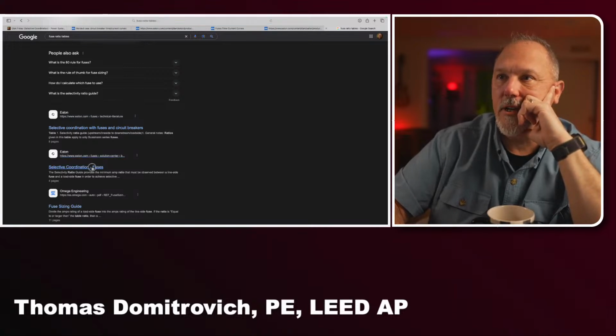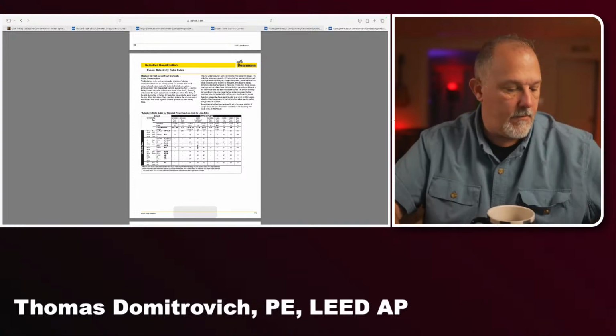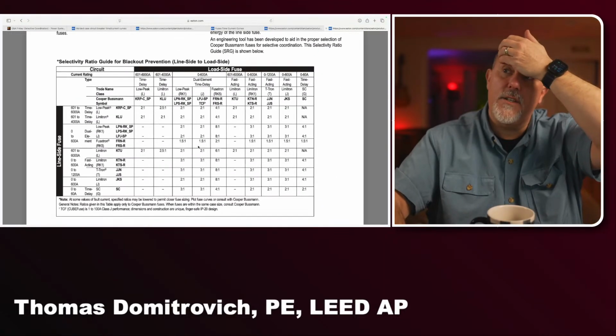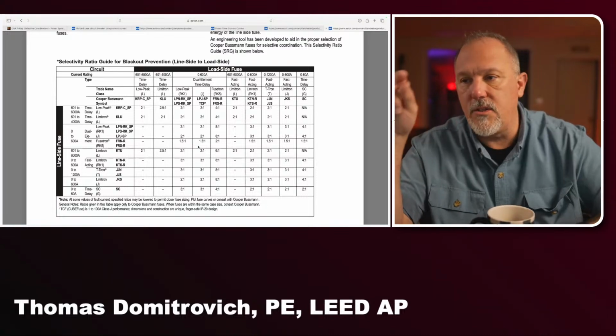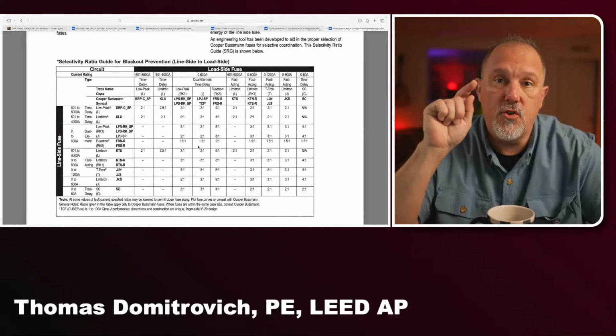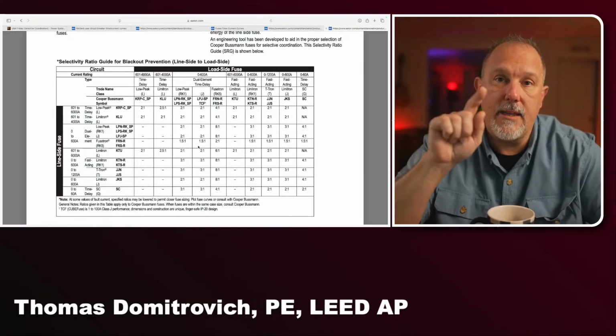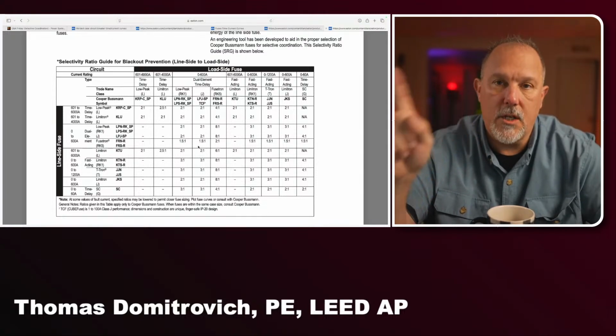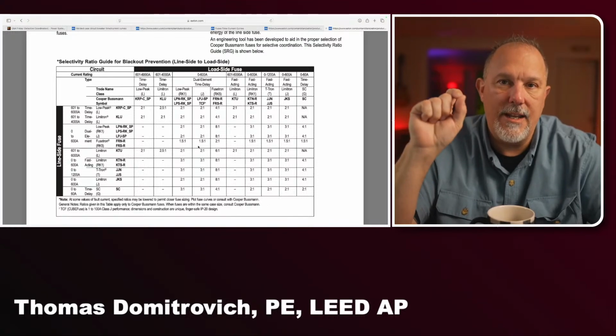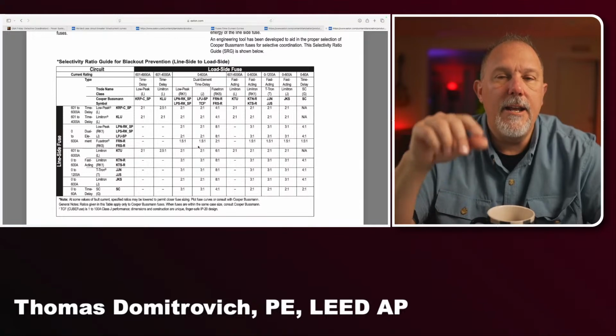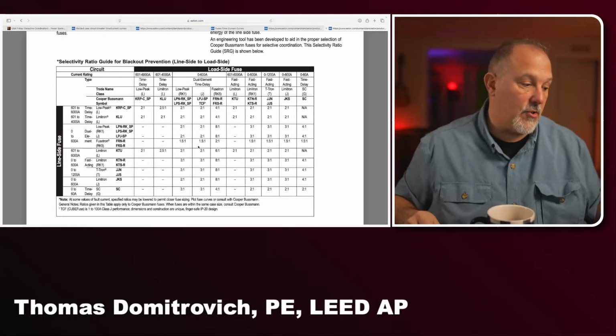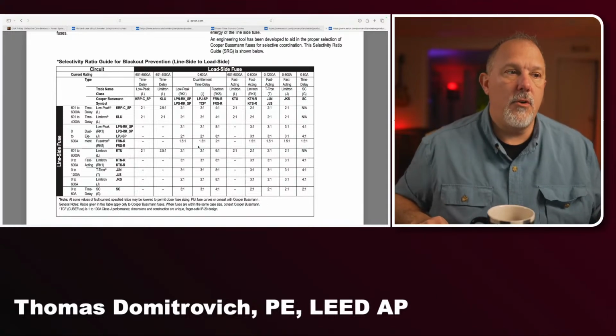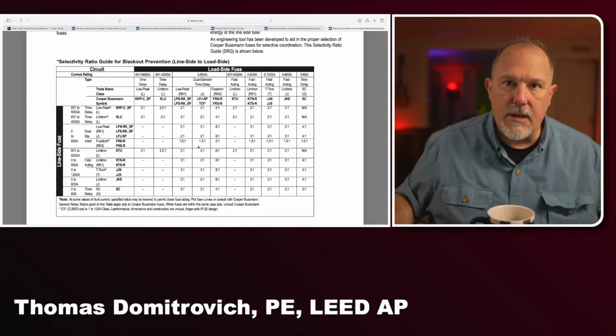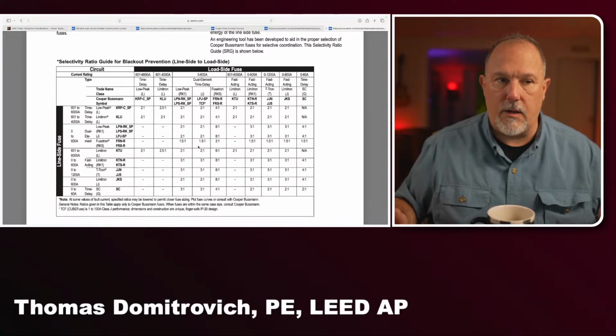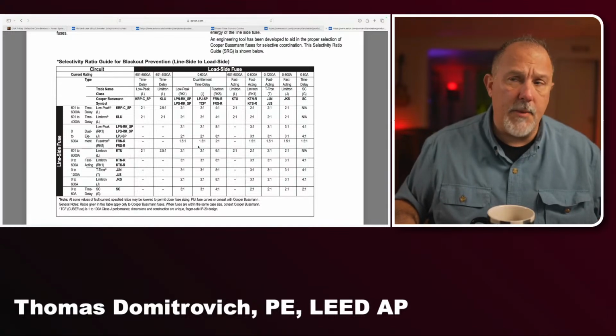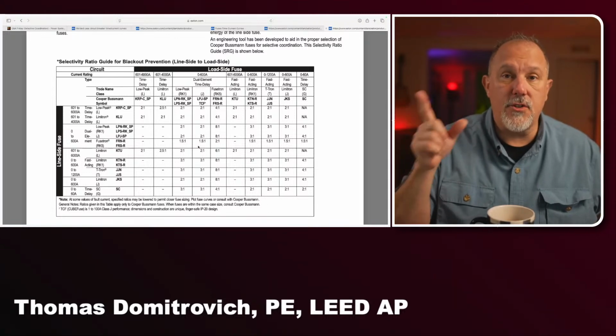So selective coordination fuses. Here we go. The fuse manufacturers have had this for a long time, and it was around 2005. What drove the tables back at that time frame was the code change. Remember, selective coordination hit the code around the 2005 NEC. And once that hit as a requirement, the breaker manufacturers realized we need to do something. So all 4 breaker manufacturers began their testing well before 2005 hit the streets, because they saw that coming. But even before that, the fuse manufacturers already had their tables.